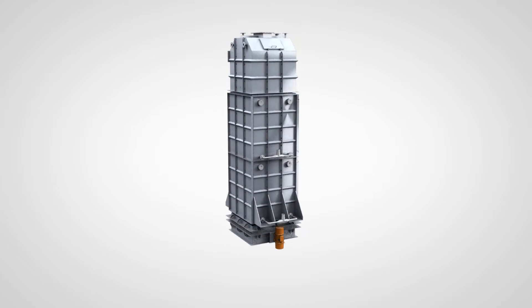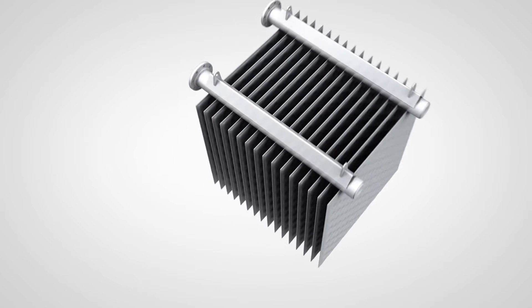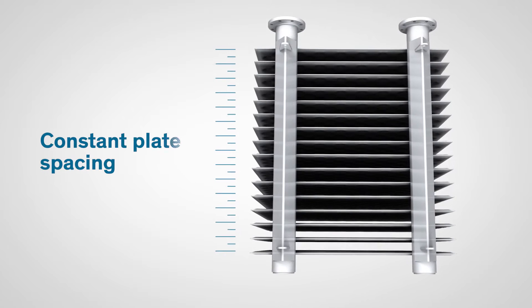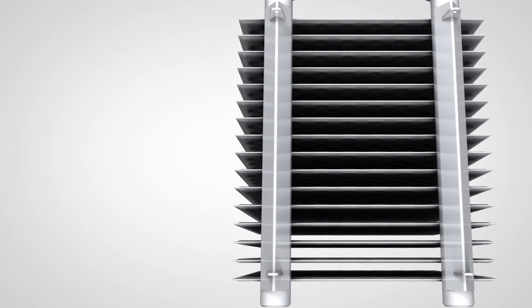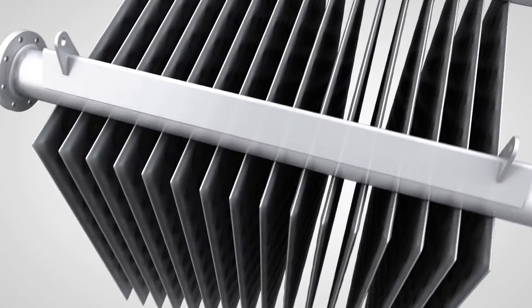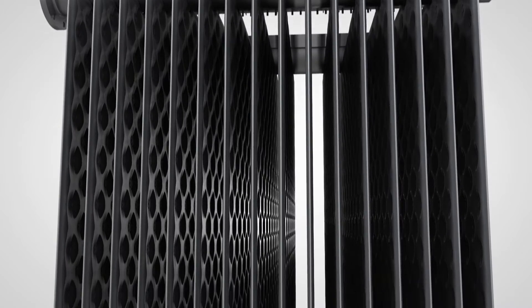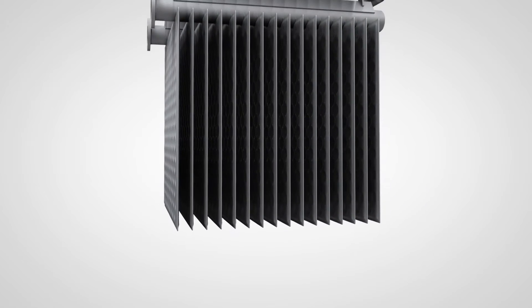Mossman developed an innovative slot manifold technique for the plate banks that offers several advantages. Constant plate spacing means more control over the heat transfer and more constant product outlet temperatures. The slot manifold technology has eliminated the need for plate supports and horizontal pipe connections, so hold-up areas that can result in the caking of solids is minimized.